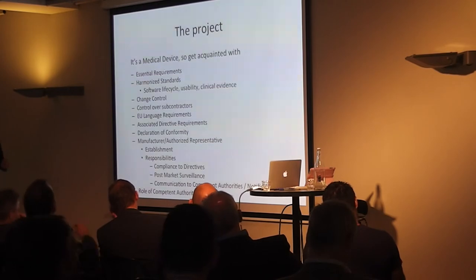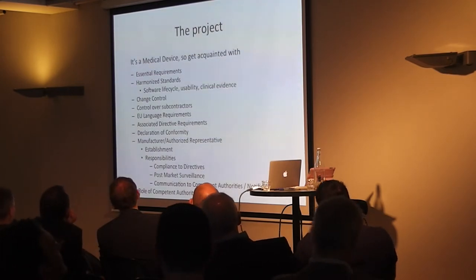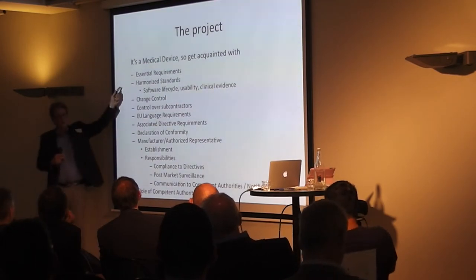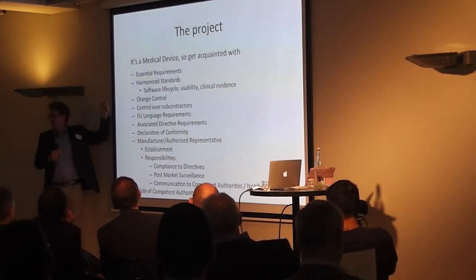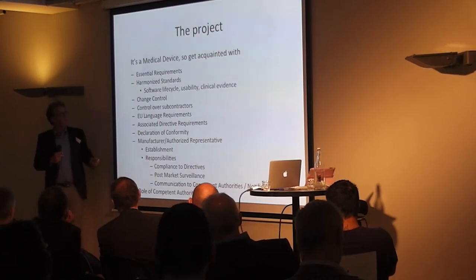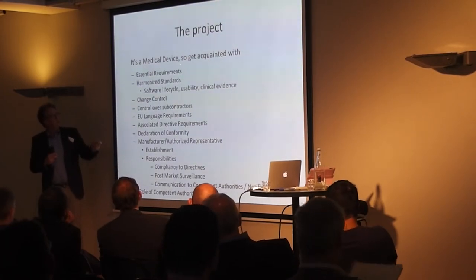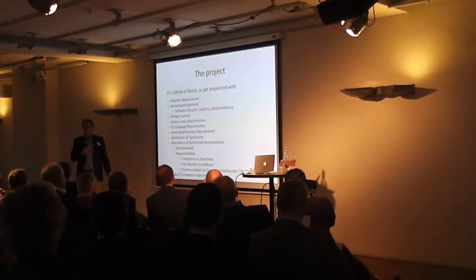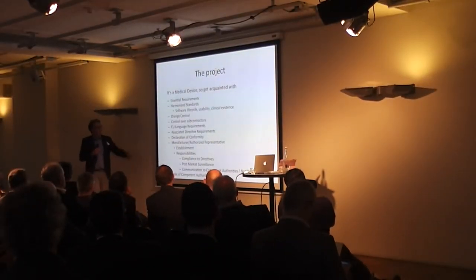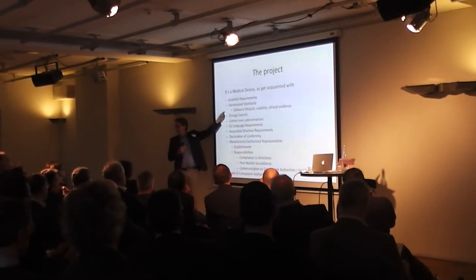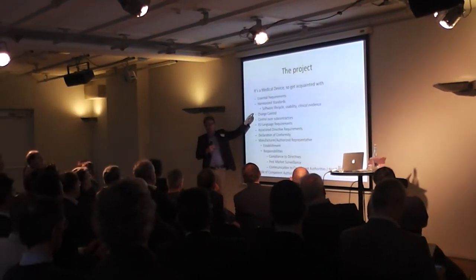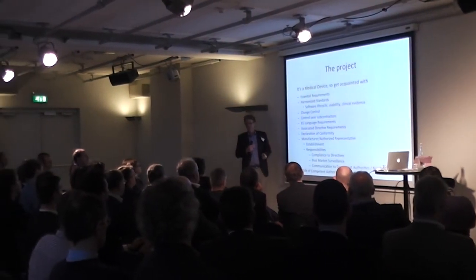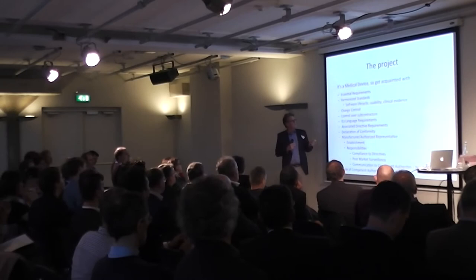So if it is a medical device, you should get acquainted with the medical device directive. Basically what it comes down to is that you need to tick off the essential requirements. The directive requirements are very, very general, very vague, and sometimes difficult to interpret. That's why harmonized standards come along, and that's why you need to apply specific medical device mandated standards related to software lifecycle.